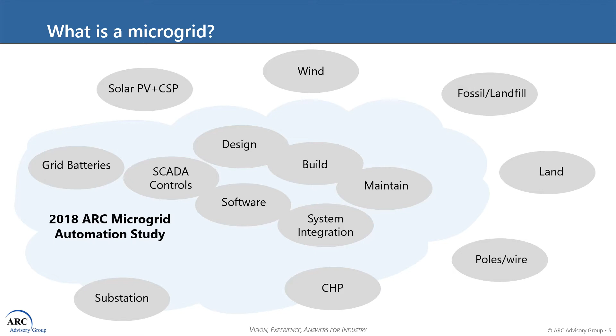In the segmentation of microgrids, ARC defines 3 levels of control. The primary level is associated with safety, protection, switchgear. This level would include items like circuit breakers, reclosers, protective related measurements like current voltage, frequency, and may include synchrophasors, if they are provided separately from the circuit breaker and recloser functions.